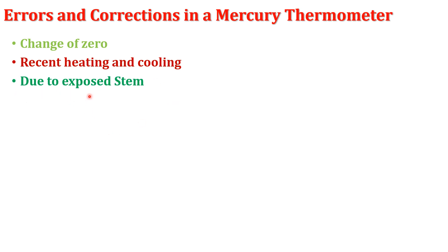The next error is due to the exposed stem. While calibrating, the thermometer as a whole is kept in the steam chamber. But while actually measuring the temperature of a hot system, only the bulb is immersed in the bath, so the observed reading will be lower than the correct reading. To correct this, the maximum possible length of the stem should be immersed in the bath.